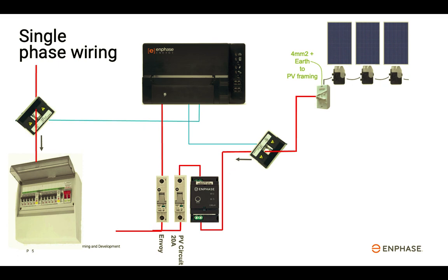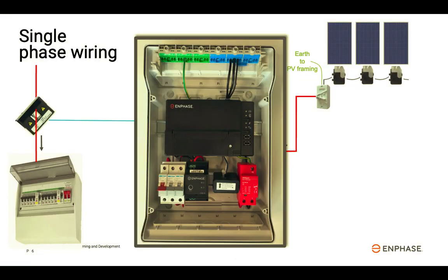Installation of subboards to house Enphase microinverter switchboard components is always recommended. A solar subboard creates installation space for the system components. It assists with AC power line communications by grouping the circuits together, and strengthens the power line signal to microinverters by enabling segregation from external load circuits.